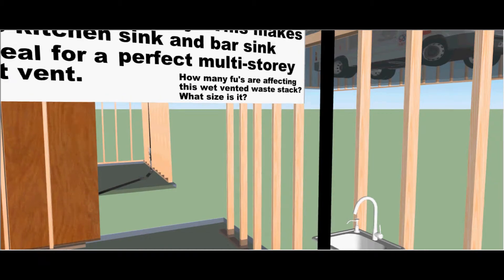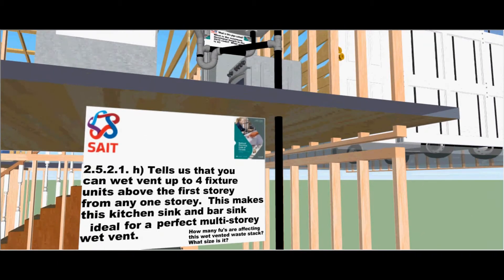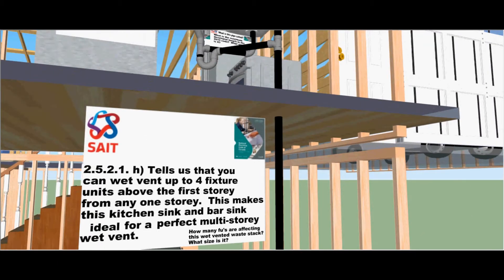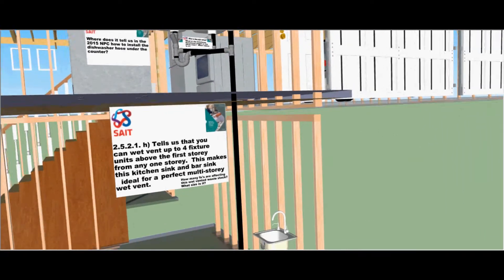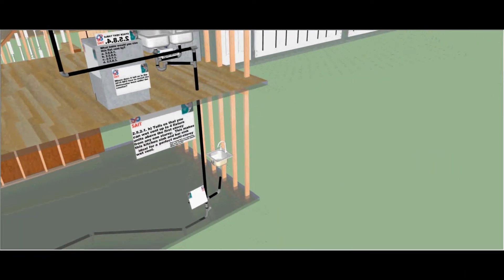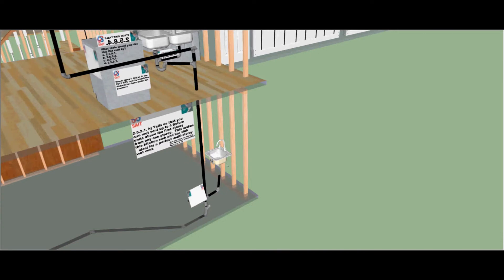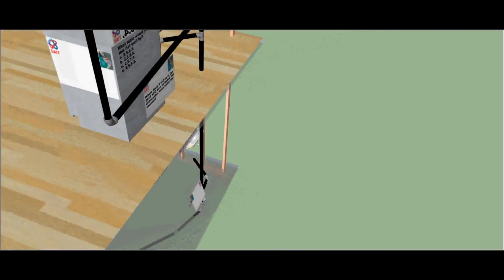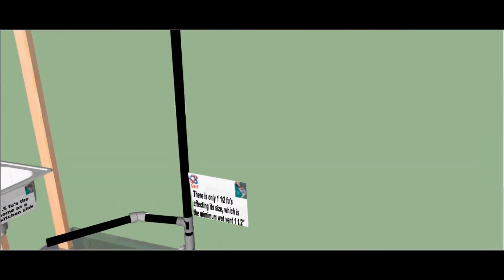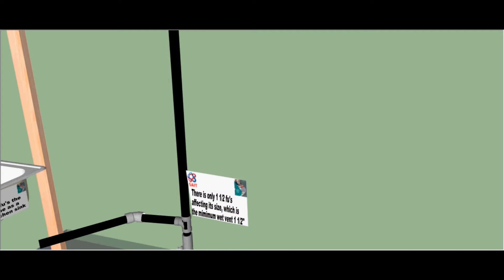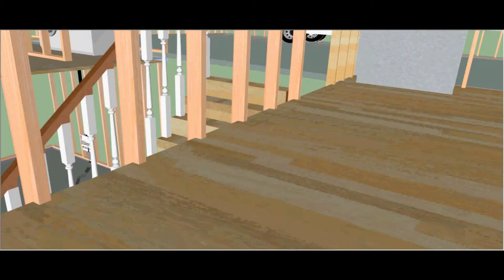How many fixture units are affecting this wet venting waste stack? What size is it? Let's zoom around and see how many fixture units are affecting it. Only one and a half fixture units affect its size. That's the minimum wet vent, one and a half inches.